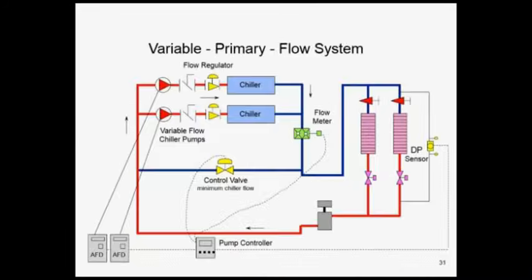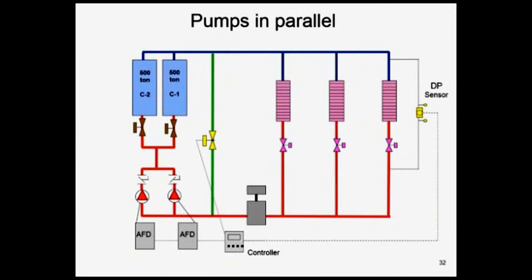How about variable primary flow systems? We get a lot of people talking about those today, where we've got one set of pumps pumping through the chillers and all the distribution. Variable primary pumping. Same thing on hot water, same thing on chill water. Now your balancing issues are entirely different again. This shows two pumps in parallel with a pants leg connection between the two in this particular situation.